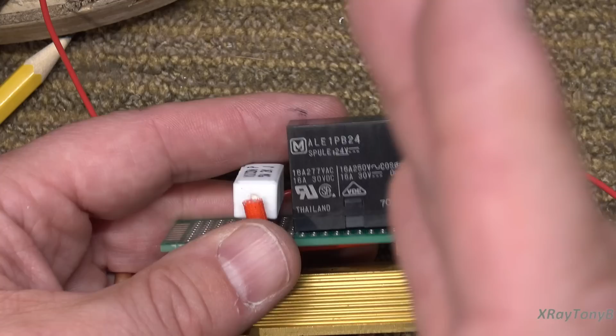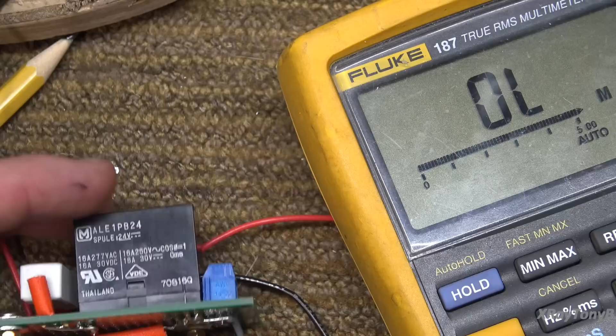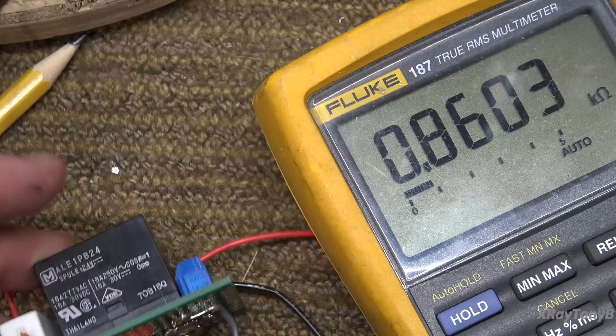Now, knowing all that, if we know the current that it operates at, this coil, like I said, under load is going to draw somewhere around 20 milliamps, 15 to 20, and we know it's 24 volts, you can do Ohm's law and determine the DC resistance of the coil. But we could also measure it with a meter, and you'll see it'll be kind of close, but it won't be perfect. So if we read it, you can see it's about 850 ohms. Okay, so that's what this relay coil is.